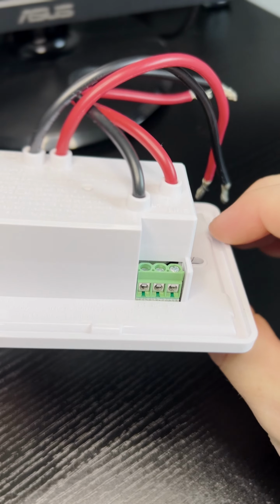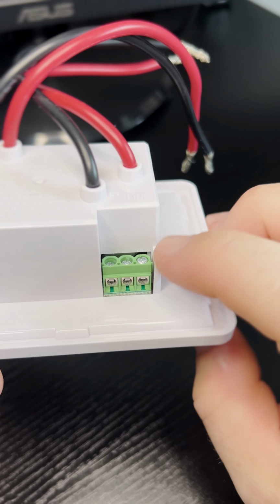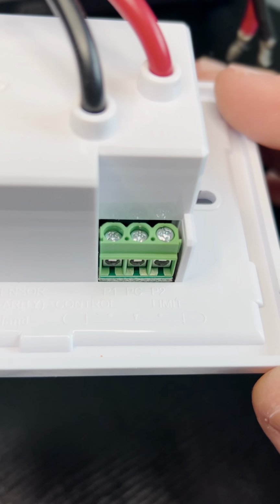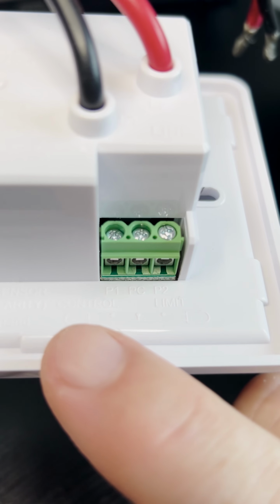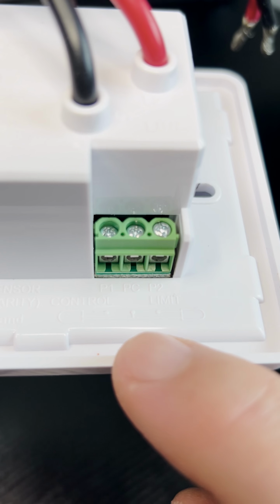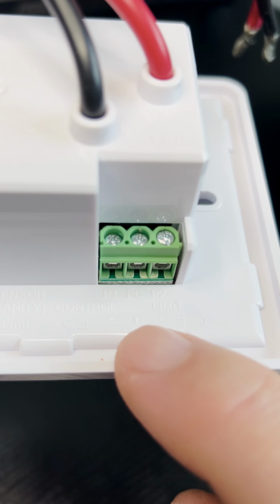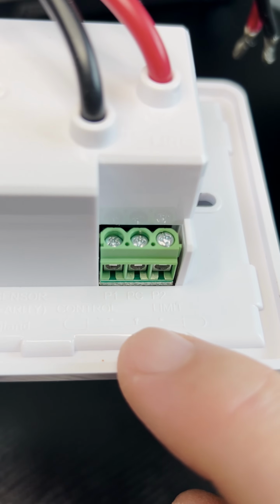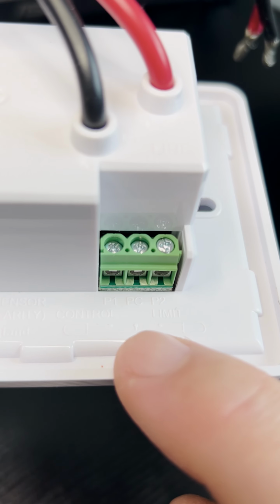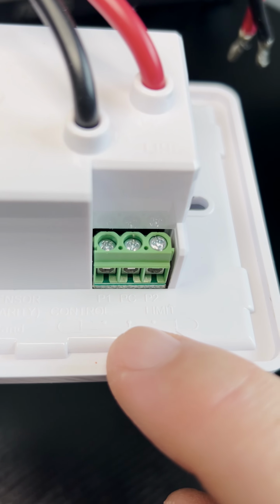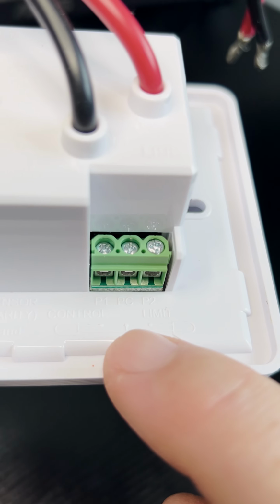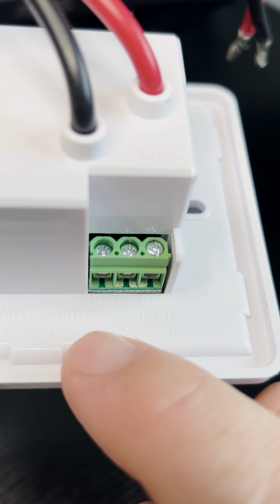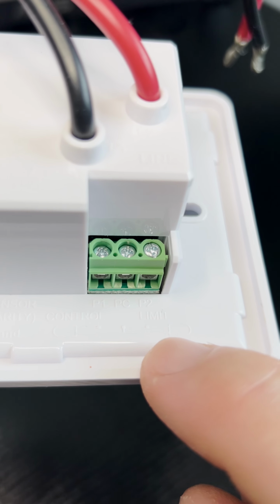Looking at the back of the StrataHeat thermostat, you'll notice there are three little terminals on the side. Each one is labeled either for control or limit, and then there's also this center terminal, which is the common power. That terminal will always need to be connected with one of the leads of the probes, the other lead in either the P1 control or P2 limit.